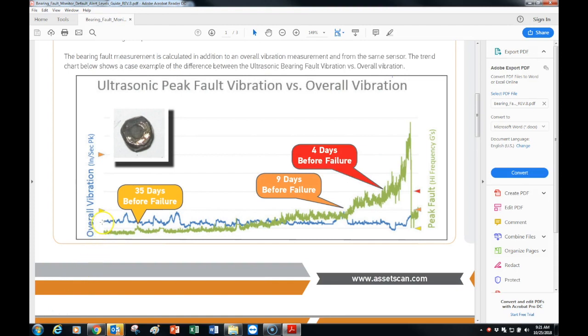So defining the scales and a little bit about this trend chart, the blue line is the overall vibration in inches per second peak. These alert limits are set at 0.2 inches per second peak and 0.5 inches per second peak for overall.